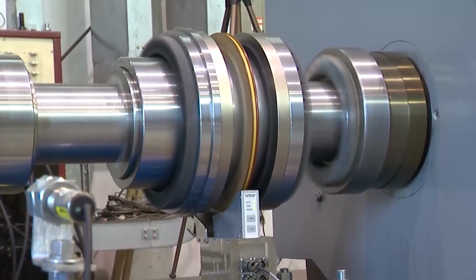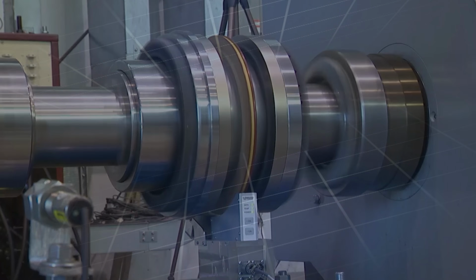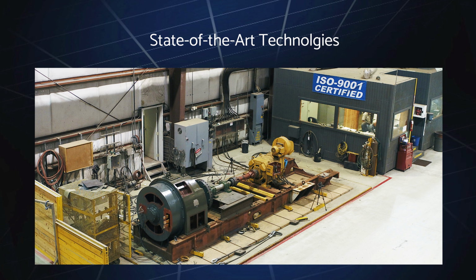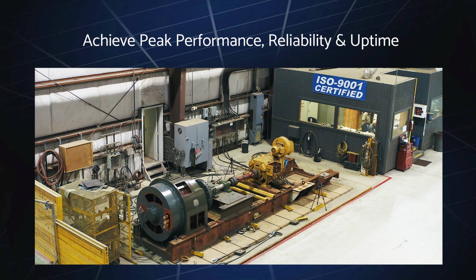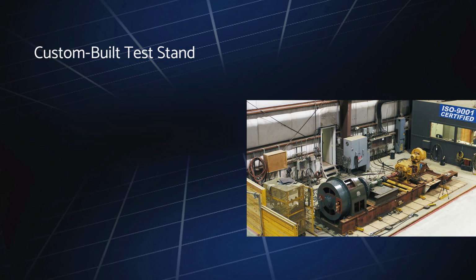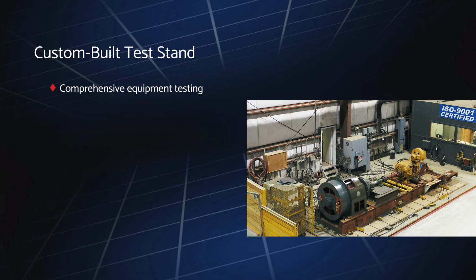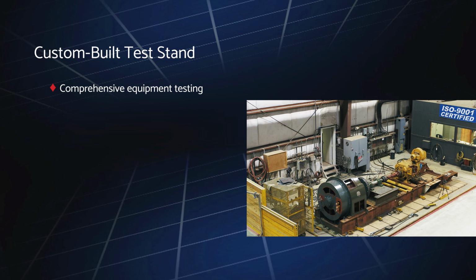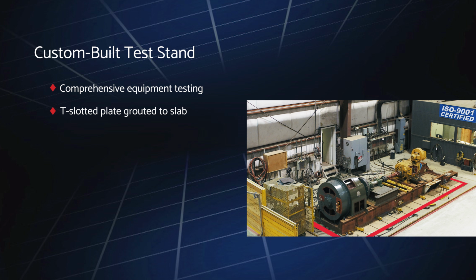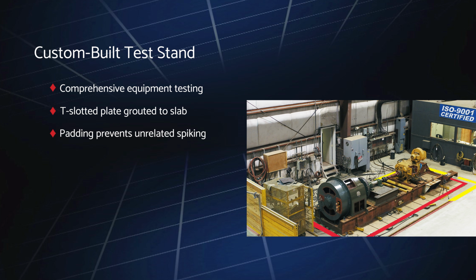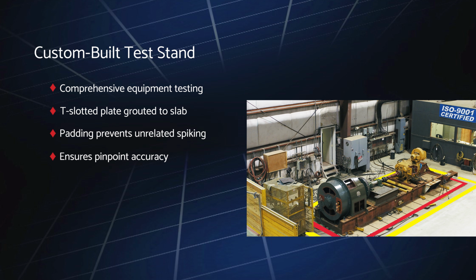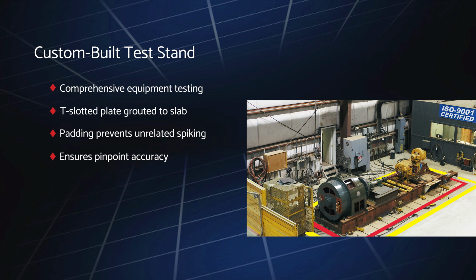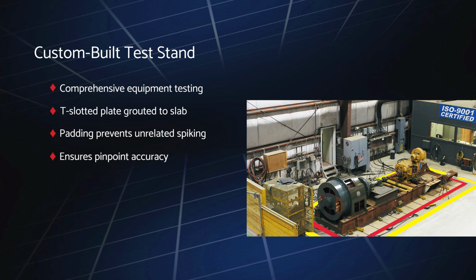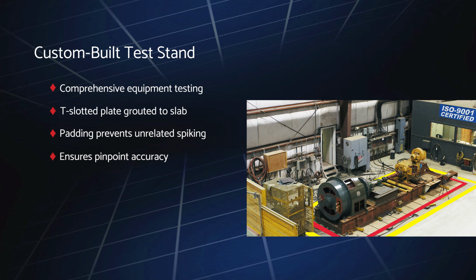Load testing is one of the most important phases in the production repair process, and Leonard utilizes leading-edge technologies to enable you to achieve peak motor and generator performance, reliability, and uptime. Our primary load test stand is custom built to handle the wide array of equipment we service, featuring a T-slotted plate grouted to a thick, rubber-padded engineering slab, which ensures pinpoint accuracy by preventing any spikes on the data acquisition system caused by unrelated work in the rest of the building.